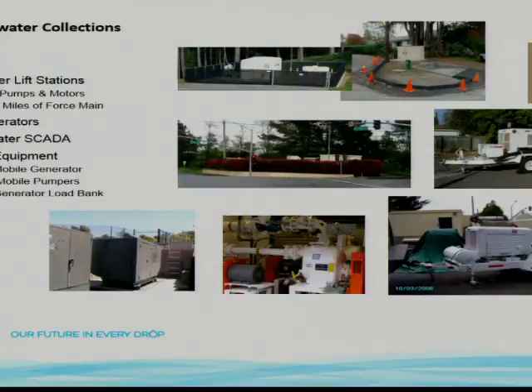Every year we take all our stationary generators and put a full load on them with a load bank to make sure they meet the parameters needed to run efficiently. That's done as a yearly preventive maintenance task.